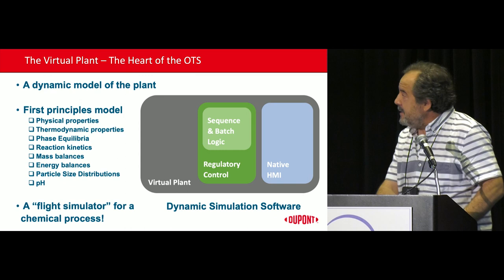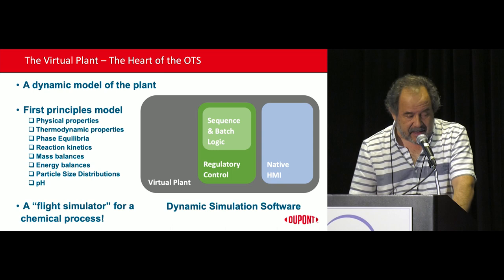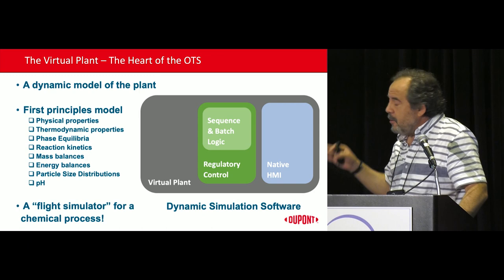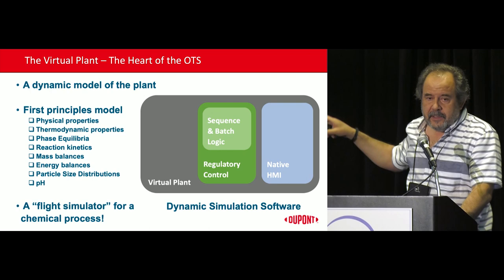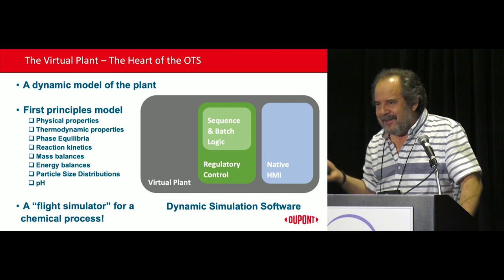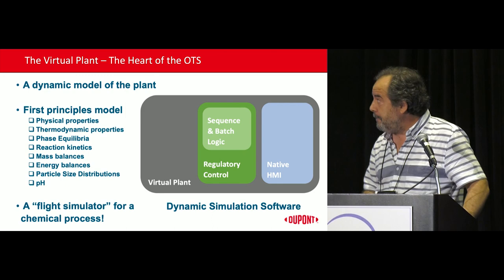At the heart of an OTS is the dynamic model of the plant. What we do at DuPont, we go with first principles models. We do all the mass and energy balances, the thermodynamics, particle size distributions if needed, the pH if needed, all the phase equilibrium — everything is in there. That's represented by the gray area in the diagram. And on top of that, in the software, we put the regulatory control that is needed to run the plant, any batch or sequences that may be needed. And of course, the software has its own HMI. In a sense, at this point, you already have a training system. But the problem is that the native HMI may not look anything like what the DCS has. But if you want to teach concepts at this point, you already have the tool that you need.